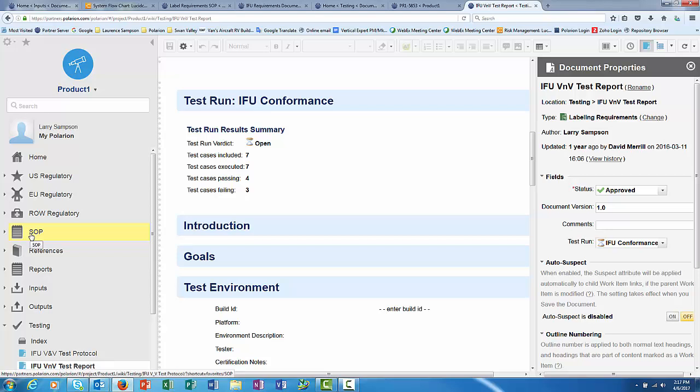So I'm authoring the requirement out of 4 source documents. Maybe I'm going to lean a little bit more heavily on number 2, and we're going to ignore number 4 altogether. Well, that's fine, but we need to have the justification captured inside the design controls so that when we come back later and somebody says, I can't believe they're doing this the way they're doing it, this document number 4 very clearly outlines that they can't do it that way. Well, when they get into the design control, they would see all 4 sources and then the justification for why it was there. So it really allows us not only to process and properly understand our design as we're creating it, but also when we come back and make changes later, we don't lose all that historical information.